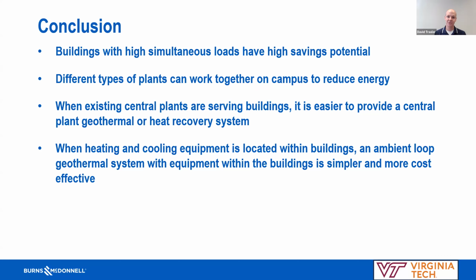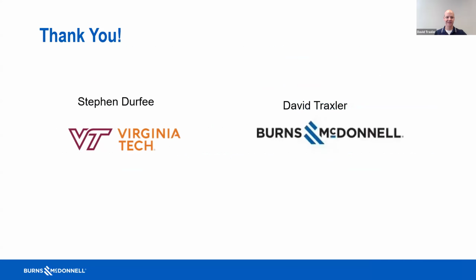Your campus can be what makes the most sense within different areas of your campus. When existing central plants are serving buildings, it's easier to provide a central plant because the buildings are already set up for it. They already have chilled water and steam-to-hot-water converters, which can be switched over to hot water, making it a much easier process. But when all the equipment is located in the buildings, like building-level boilers and chillers, then an ambient loop makes a lot more sense and is less costly to install. Thank you very much.